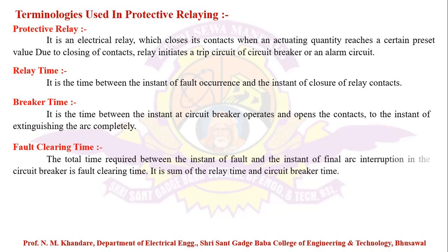Next is the fault clearing time. It is the total time between the instant of fault occurrence and the final arc interruption in the circuit breaker. The fault clearing time is the sum of the relay time and the circuit breaker time.